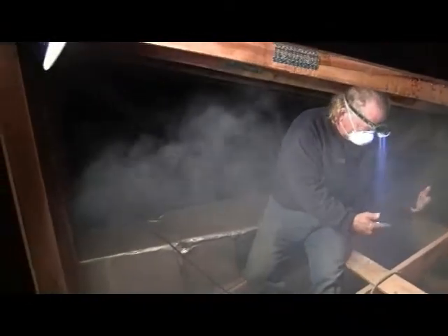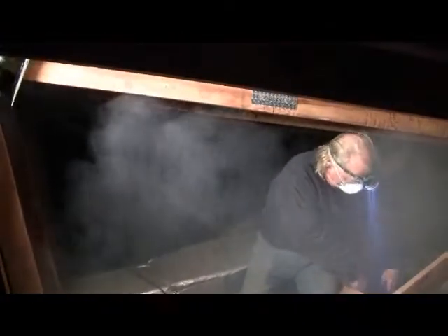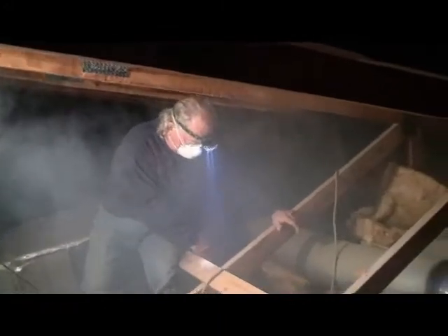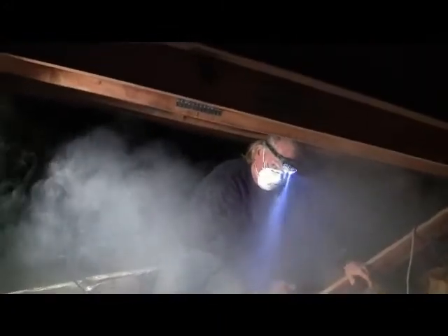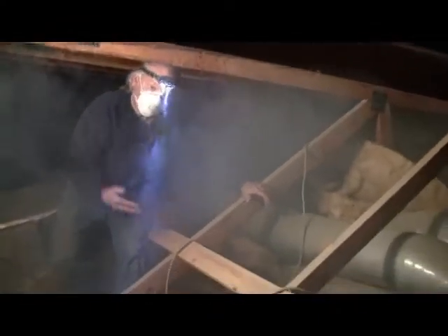And this wall cavity goes all the way from the attic down past the floor of the stage to the ground, to the cement down below it, and it connects directly with the return plenum of that furnace. So right now, because we're pressurizing the ducts, it's blowing smoke out into the attic. When the system is running, it is sucking air from the attic all the way to the furnace to try to recondition out the hot air of the summer or the cold air of the winter.